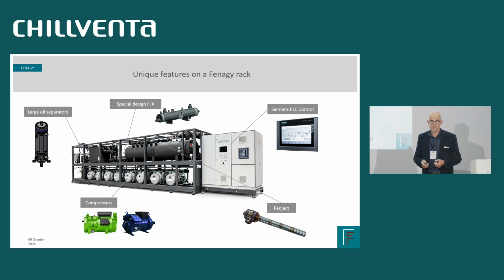The rack itself, horizontal receiver, a number of compressors, ejector technology, most probably, because heat pumps are very happy with ejectors, because we can use them all the time because the high pressure is already there, driving the refrigerant through the ejector, recovering energy from the system.